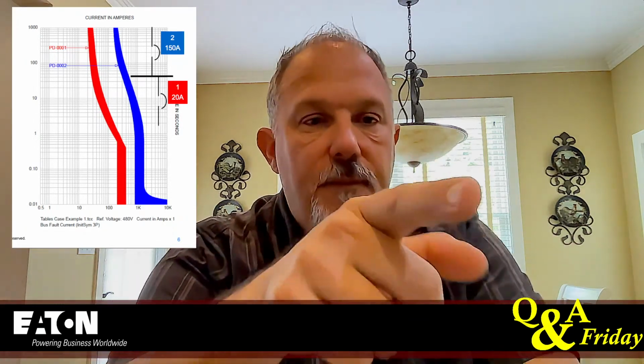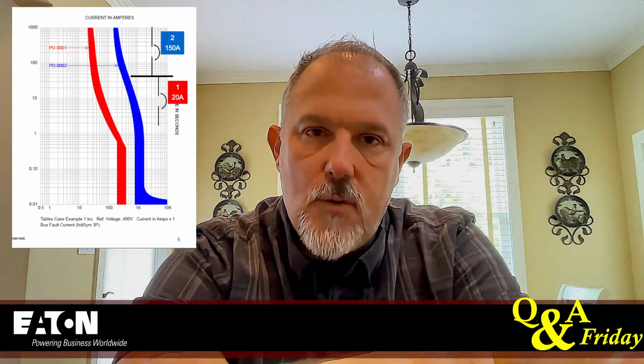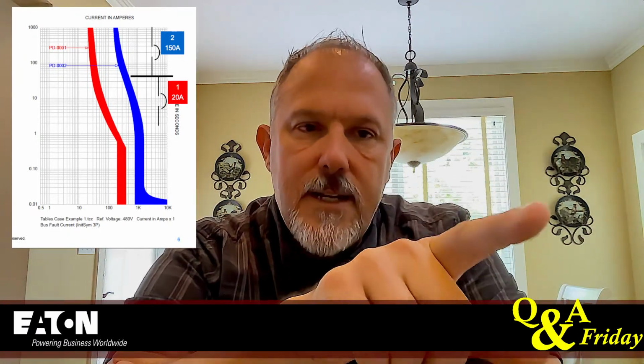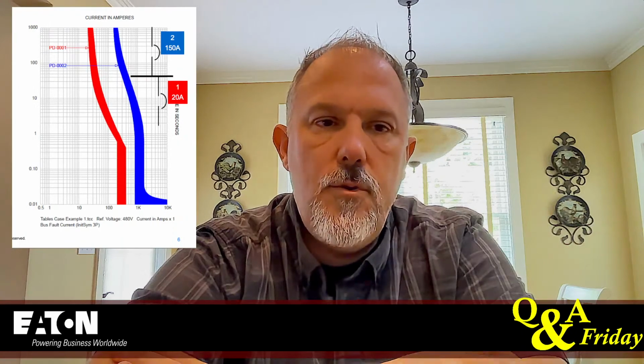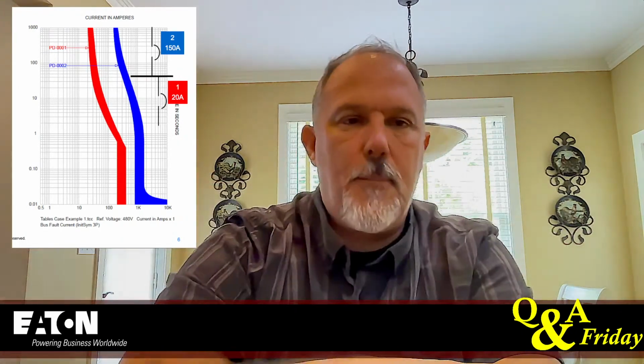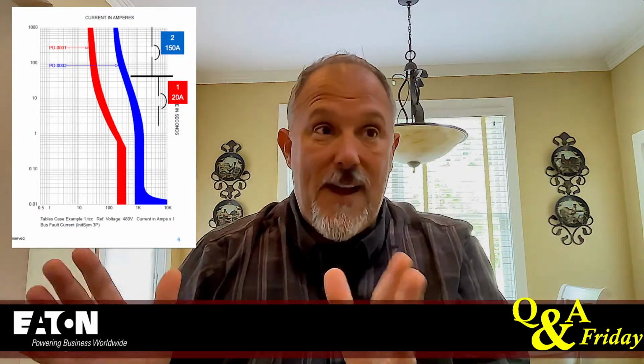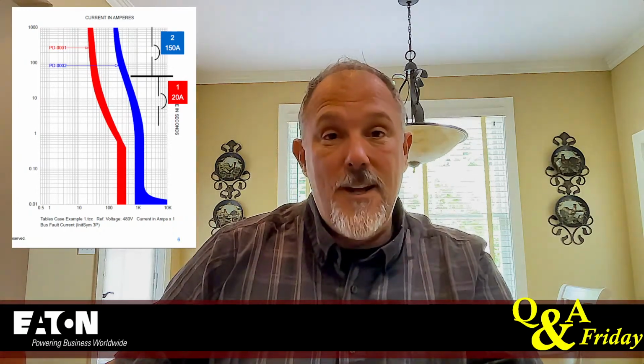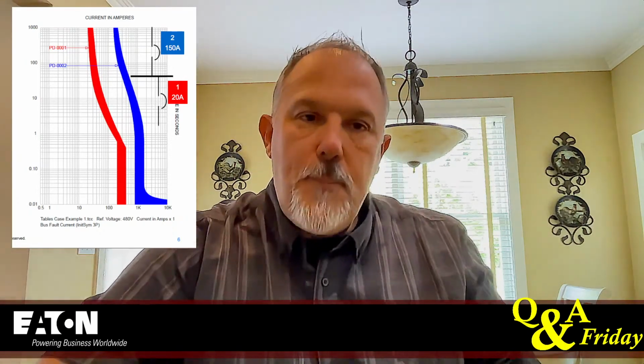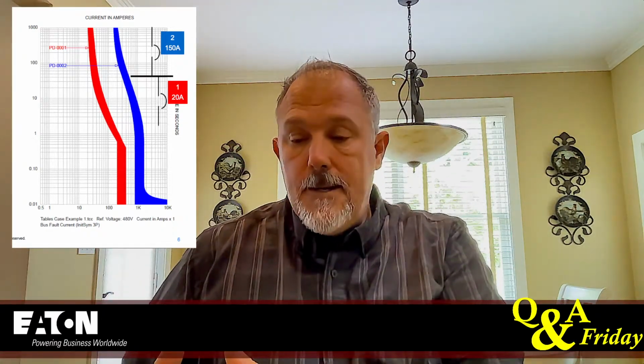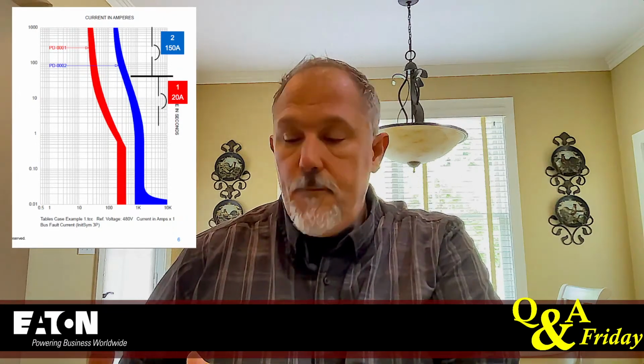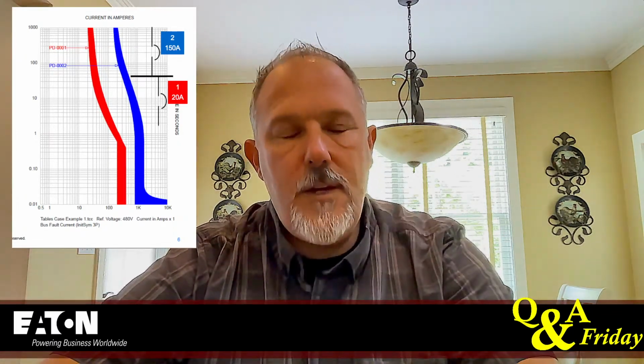Now here's the problem. That 150 amp breaker is not on the same equipment. It's not like it's a main. What's connecting that 150 amp breaker to that bar, where the 20 amp breaker is, is a conductor. In fact, it's 150 amps worth of conductor based upon conditions of use. So here's the issue you run into. You beef up that breaker, you put in a 400 amp frame breaker, or maybe a 600 or an 800 amp frame breaker, and you dial it down, but you might not be able to dial it down to 150 amps. So what do you have to do? You need to put in a larger conductor.